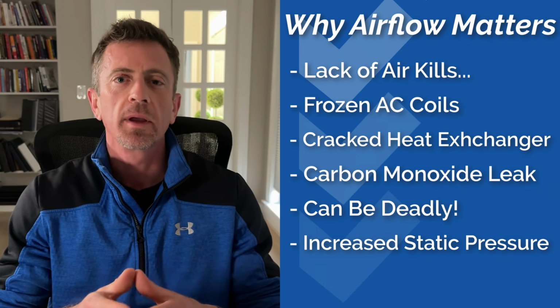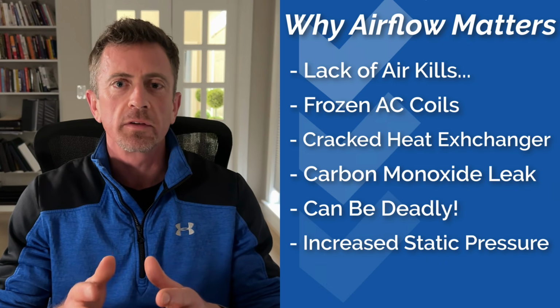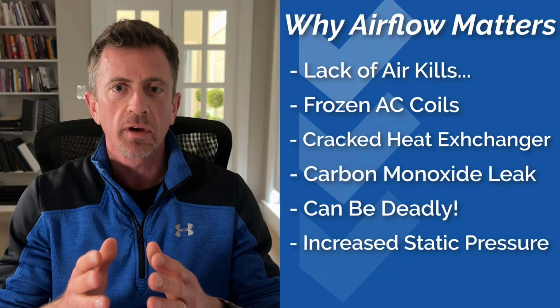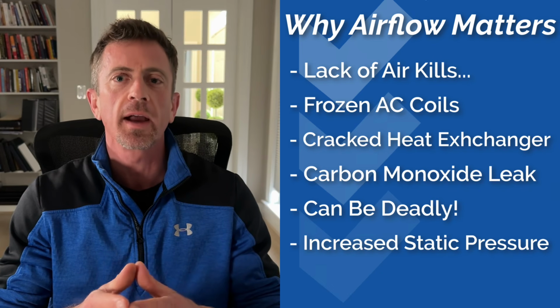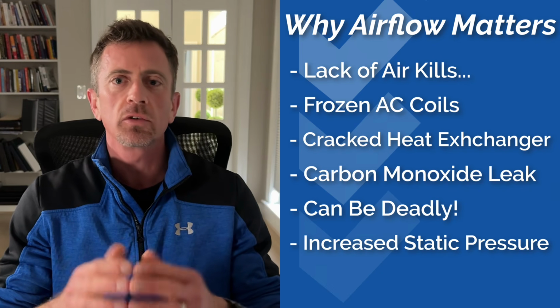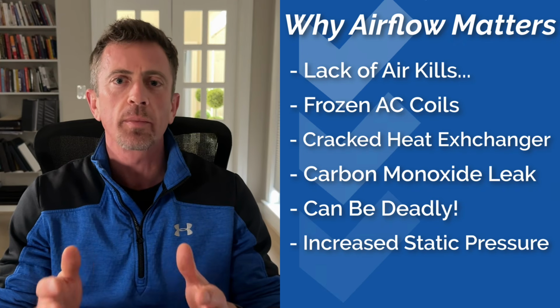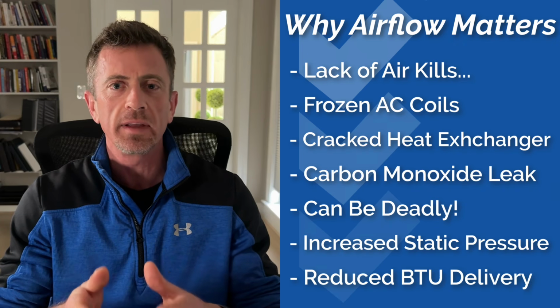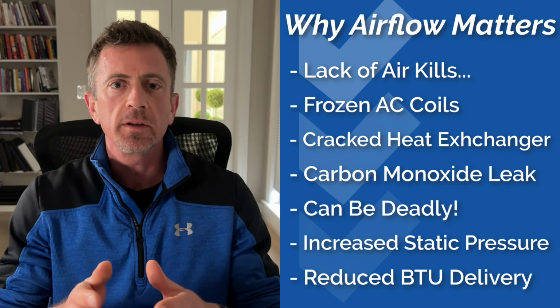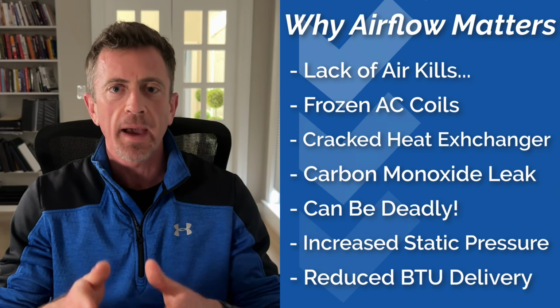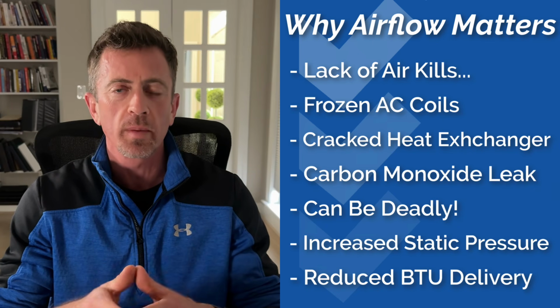And here's the kicker. HVAC systems are rated to deliver a specific number of BTUs of warm or cold air to the rooms in your house. Any duct leakage, reduced airflow, or lack of proper insulation directly reduces the BTU delivery. This means you're not getting the efficiency and output capacity that the manufacturer says your equipment should provide.